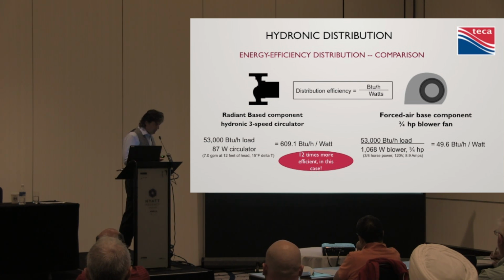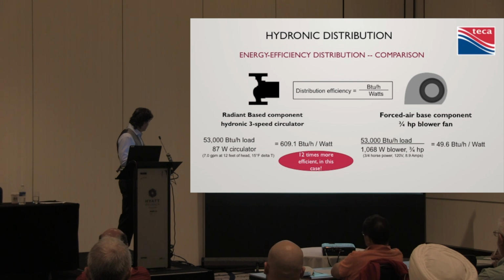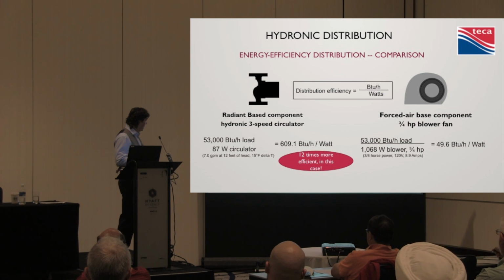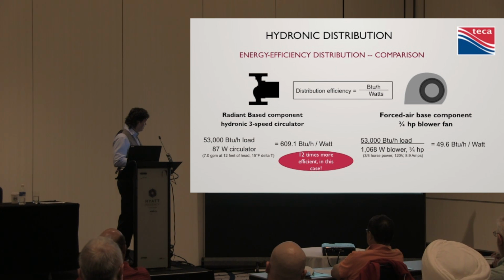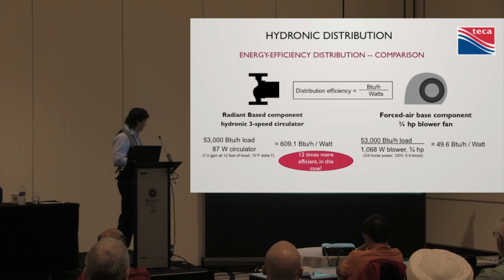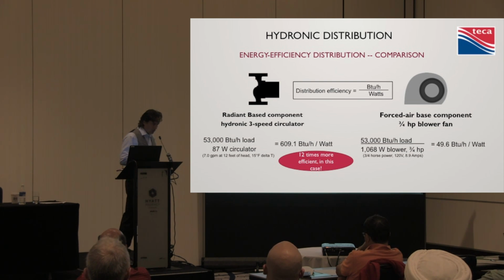Most likely, and I'm talking using radiant, fan coils, whatever it is you want to use. You've got to move the water, you've got to move that many BTUs. That circulator will do it. So we're assuming 7 GPM, gallons per minute, at 12 feet of head. That would do a radiant system right there. So that's a lot of pressure drop, actually. So we're forcing a lot of water. Even having said that, we use 609 BTUs per watt. So compared to forced air, if we're using the same amount of loading, so 53,000 BTUs, we're transferring the same amount, but to run a 3/4 horsepower blower is using significantly more power. So this is the beauty of hydronics. It's a much easier way to move energy around.